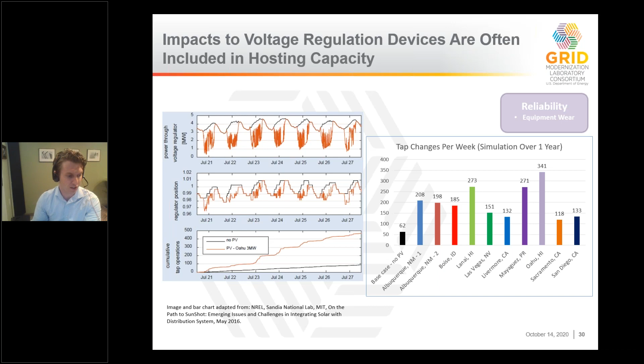Finally, in terms of technical impacts, there's potential for constant changes in DER output based on cloud cover for solar or changes in wind, causing output fluctuations. If there's equipment nearby intended to respond to voltage changes, these fluctuations can cause the equipment to operate very frequently. On the right is a study performed by NREL looking at how many times voltage regulation equipment—which mechanically switches metal contacts—would need to change taps, and the resulting wear and tear we need to watch out for. That's a common threshold for hosting capacity as well.